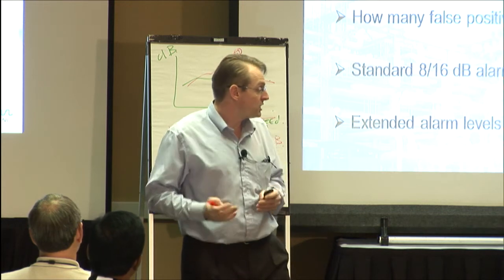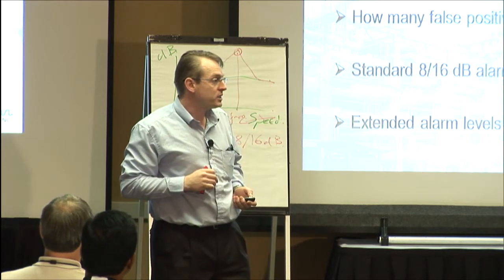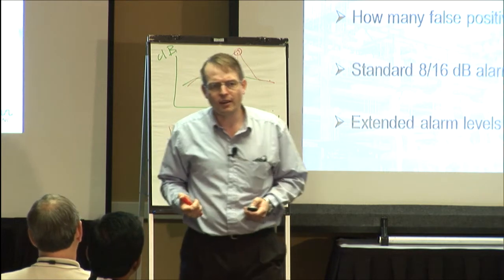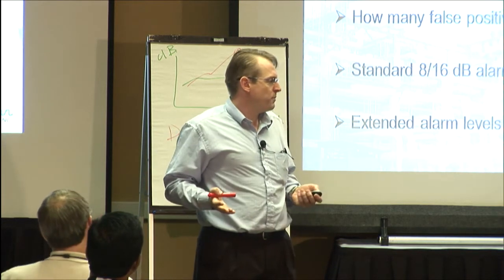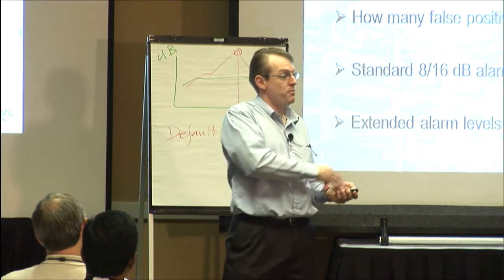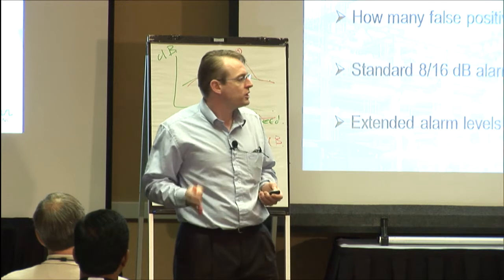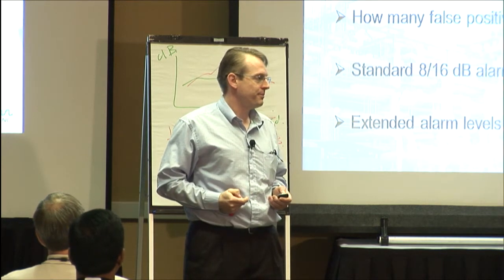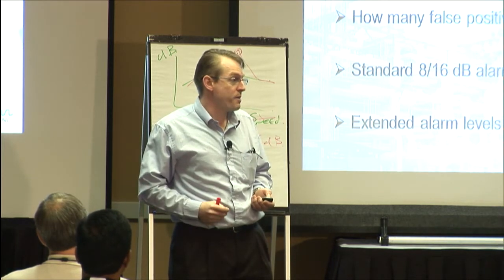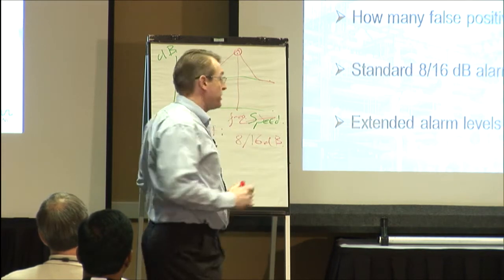So instead of going 8, 16, maybe I'm going to go 10, 20, or if it's something like the pulp screen, you might say, well, is that critical, isn't it? You might say, well, actually, when I stop and think about it, if it's 12 dB, it's either going to be one of two things. Just a little high because it's going too fast, or faster than my baseline, or it means I'm a little bit past my lubrication alarm. What's your action going to be at that point anyway? Can you do anything else other than lube it? So does it really matter? Okay. Well, are we going to do anything else other than that?